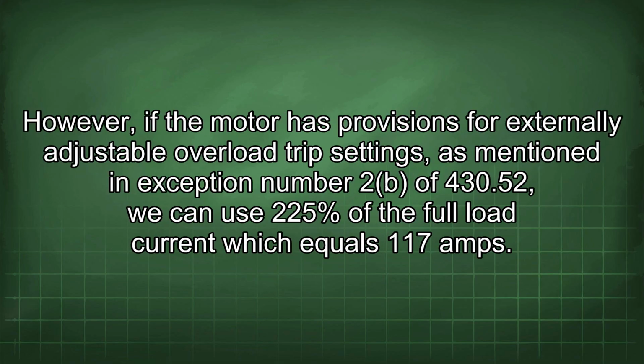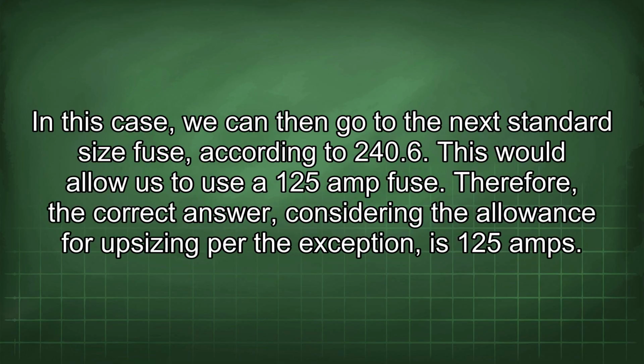However, if the motor has provisions for externally adjustable overload trip settings, as mentioned in exception number 2(b) of 430.52, we can use 225% of the full load current, which equals 117 amps. In this case, we can then go to the next standard size fuse according to 240.6. This would allow us to use a 125 amp fuse. Therefore, the correct answer, considering the allowance for upsizing per the exception, is 125 amps.